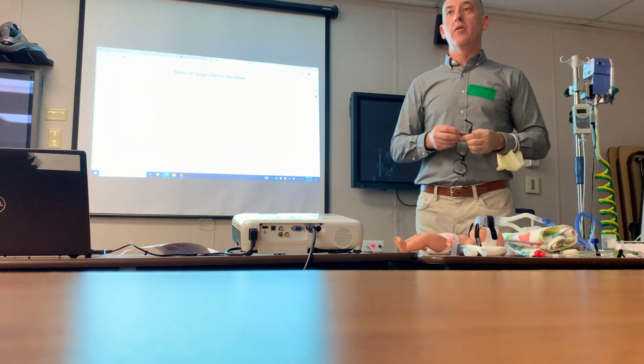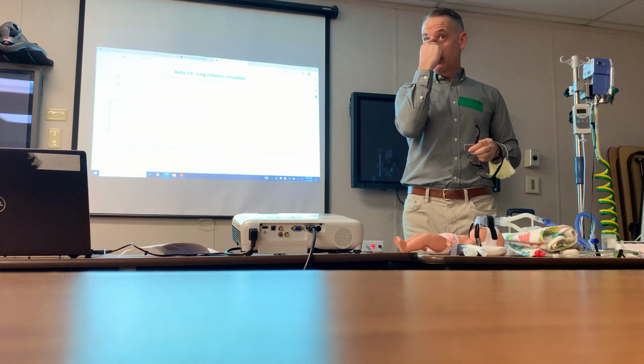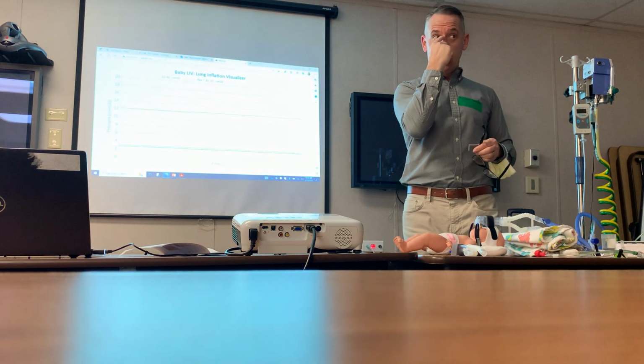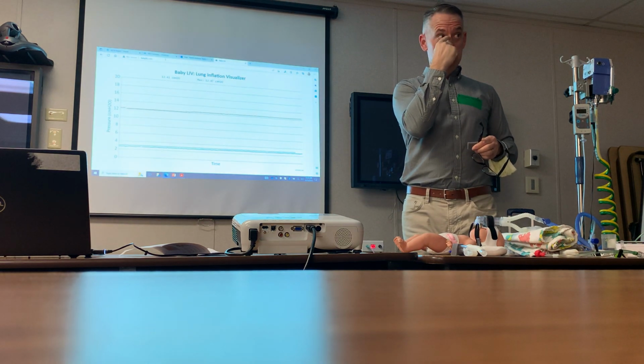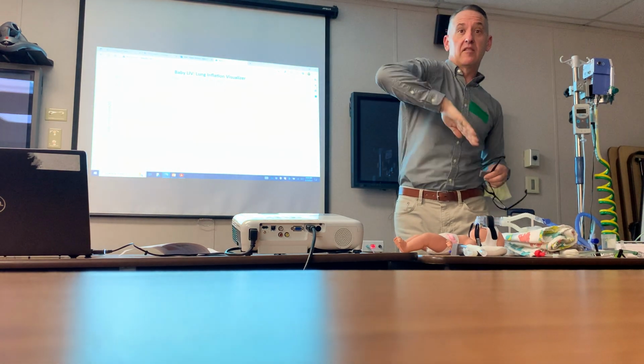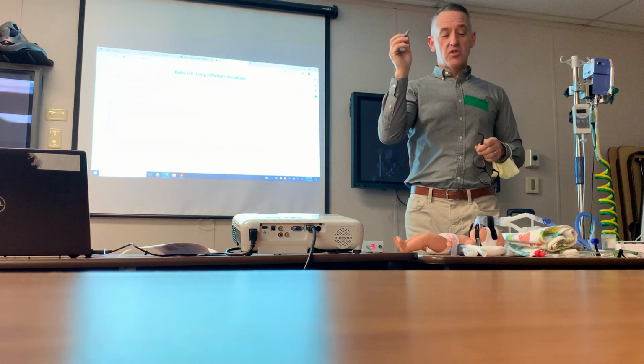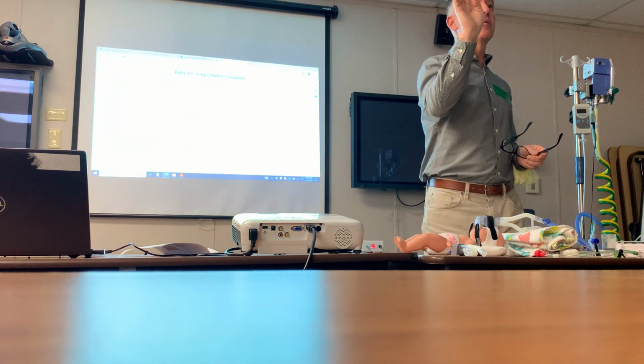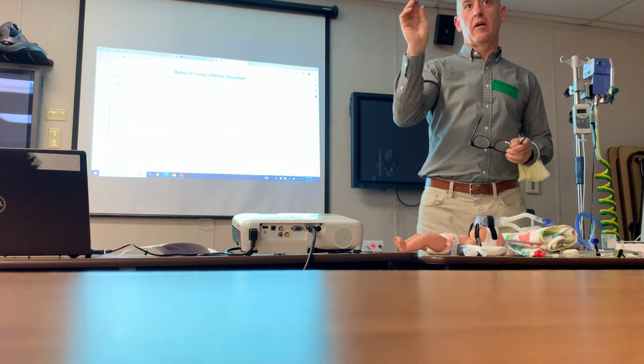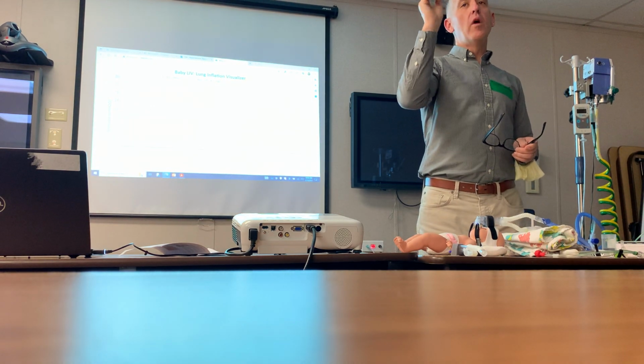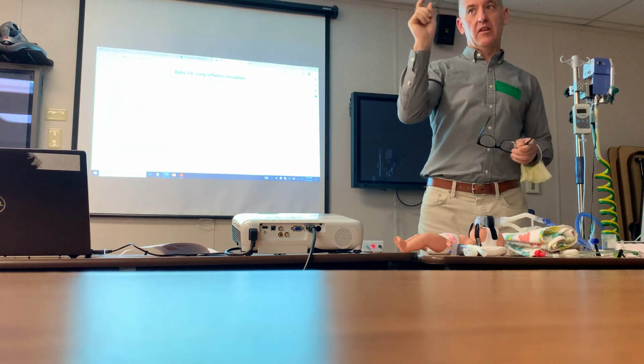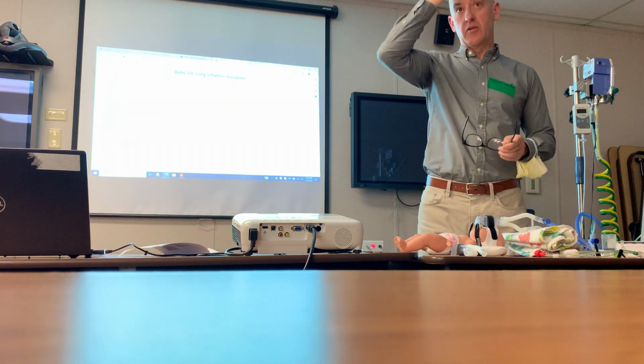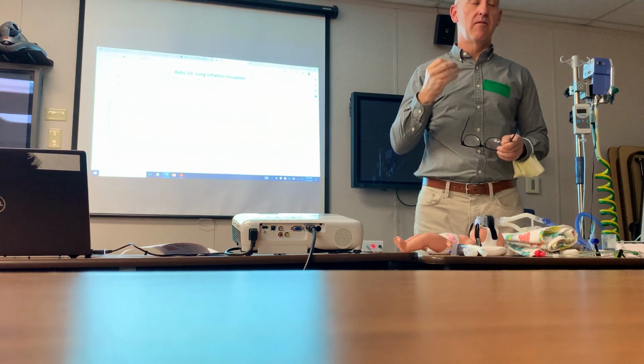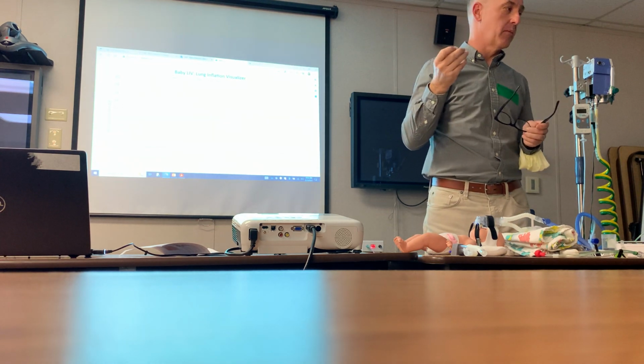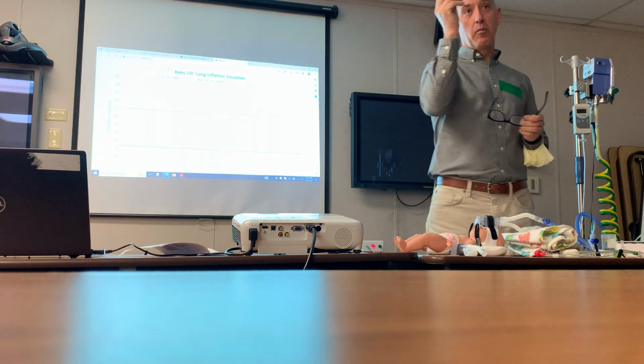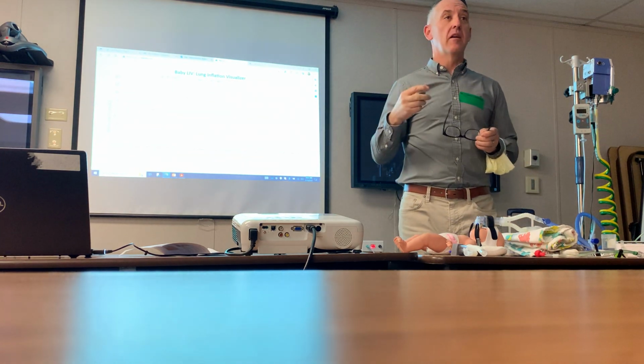The third and most common one, if you guys have used this interface, is breakdown right here. Anybody know why that happens? It's because of the mask. It's because the mask is cantilevered down. If you've used our interfaces, you've noticed it comes with these foam strips. If you've ever seen these, we'll have to retrain on that. When you use the mask, you always have to have at least one foam strip in there, and that keeps it parallel with the face of the baby. If you didn't know that, that's okay. That's our job as a company to make sure to train that. But the one foam strip with the mask will make sure it stays parallel with the face.